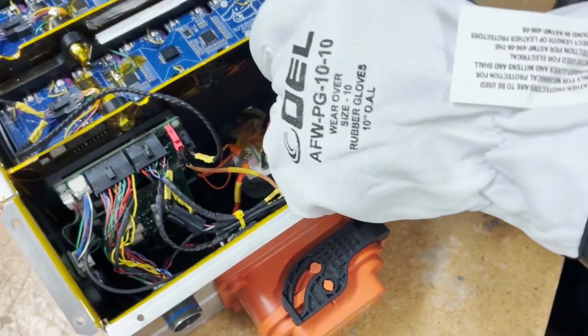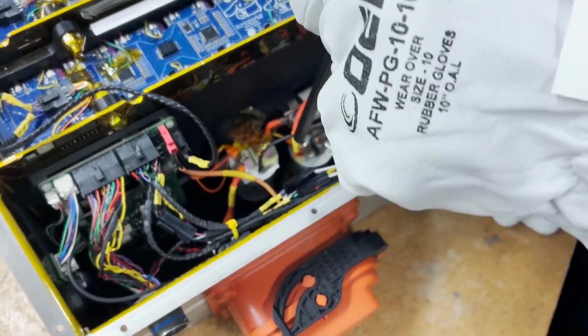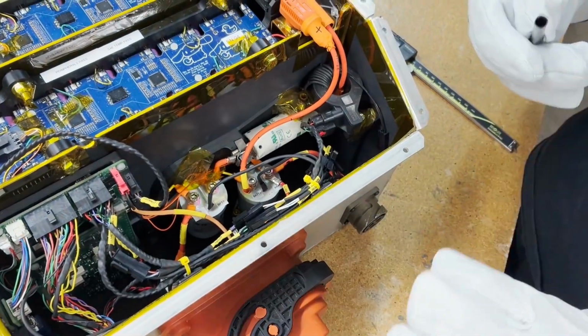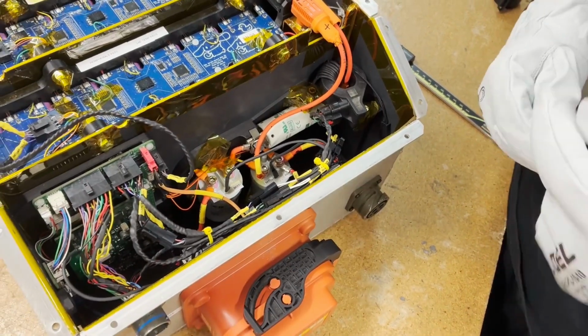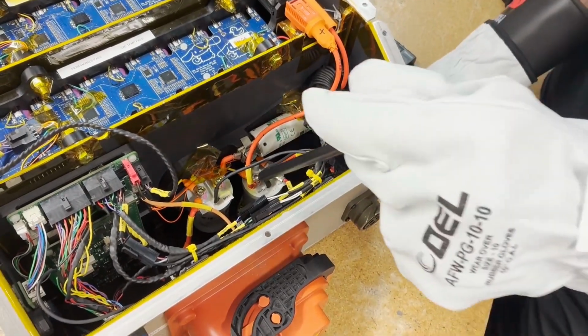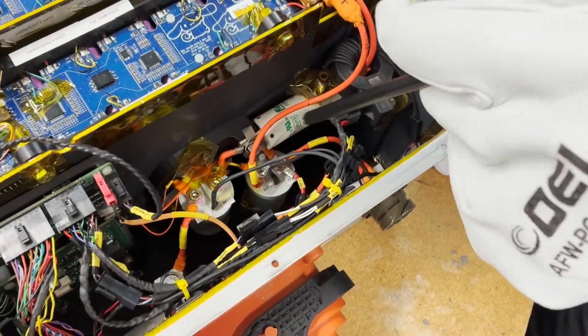As for the low voltage and high voltage wiring, you can see that we are maintaining a gap between our low voltage and high voltage wiring, and there's barrier material in the heat shrink of the wire itself, visible at the closer points around the contactors.